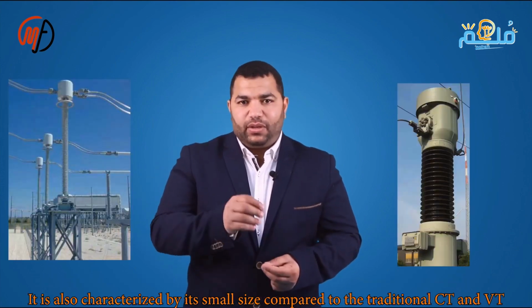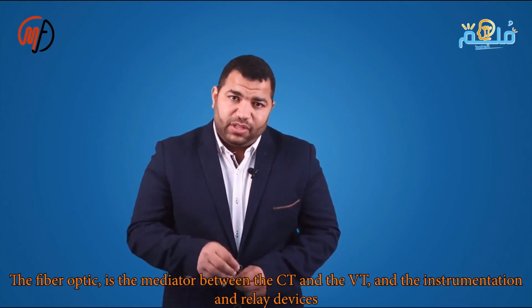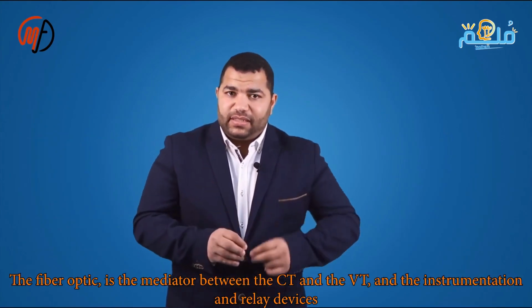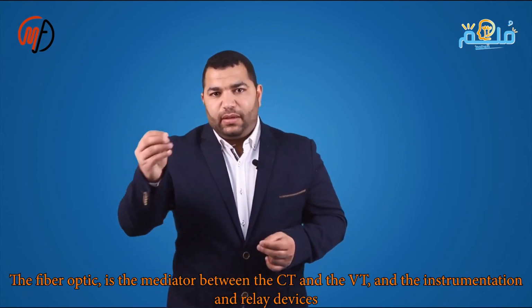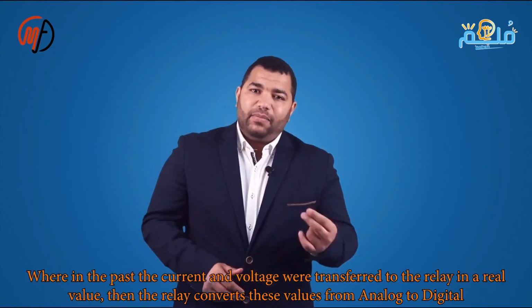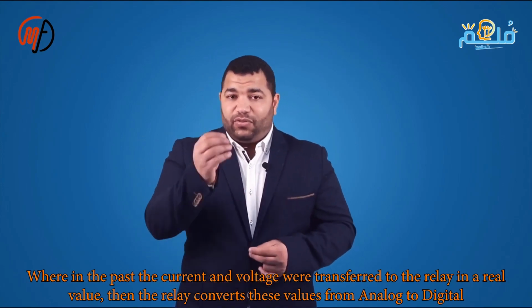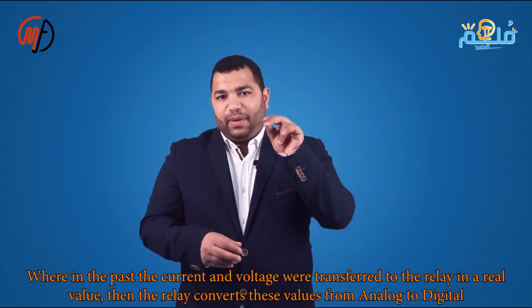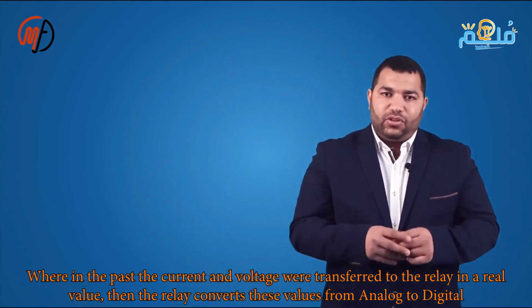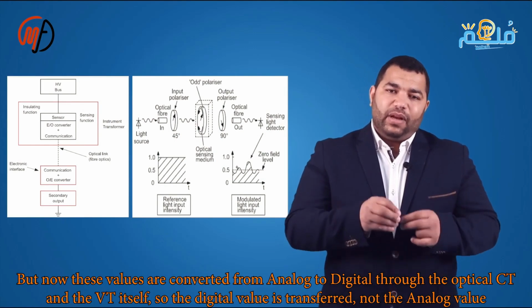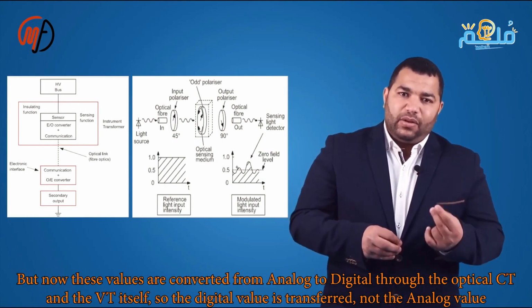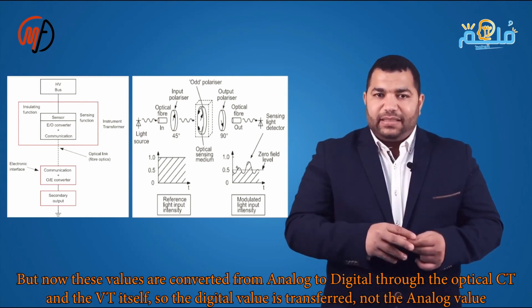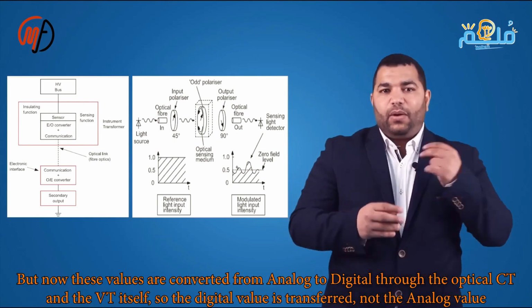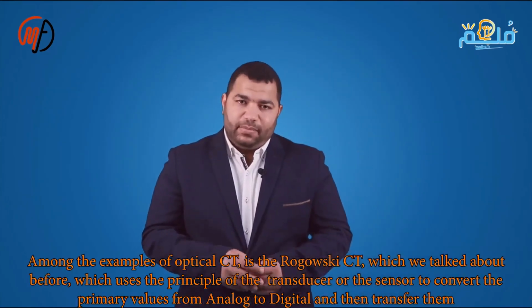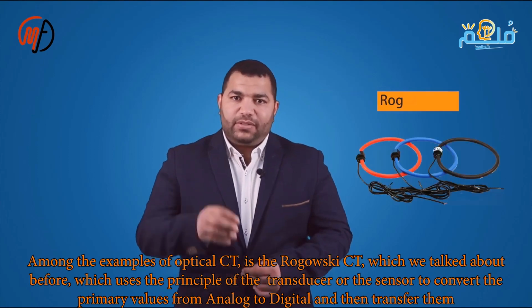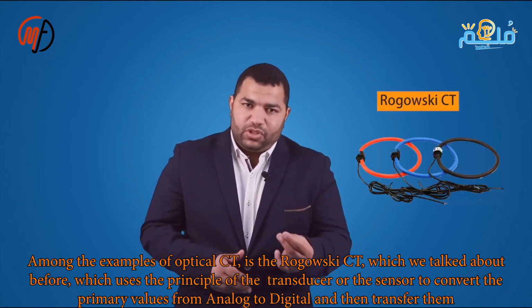Previously, analog current and voltage were relayed and converted to digital. Now CTs and VTs directly convert to digital for transmission. The Rogowski CT exemplifies using a transducer for digital conversion and transmission. This is part of the electricity system from generation to consumption. These values are now converted from analog to digital through the CT and VT, transmitting digital instead of analog values. This is part of a system involving electricity generation, transmission, distribution, and consumption.